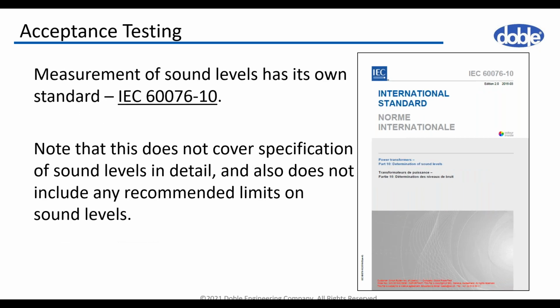Another example of a test with a specific standard is sound level measurement. The test is explained in IEC 76 Part 10, including requirements for the measuring equipment, test procedure, and how to calculate the final results. However, something you won't find in this standard is specific limits for sound level, and these should be specified by the customer at the beginning of the procurement process.